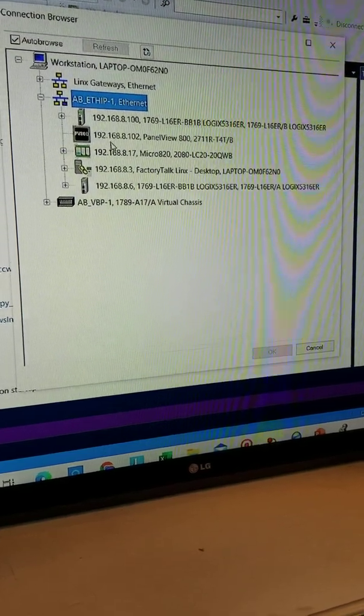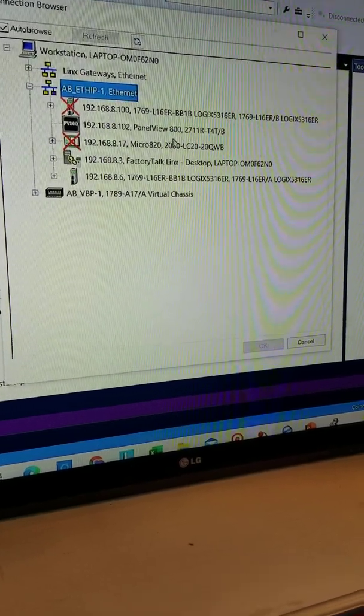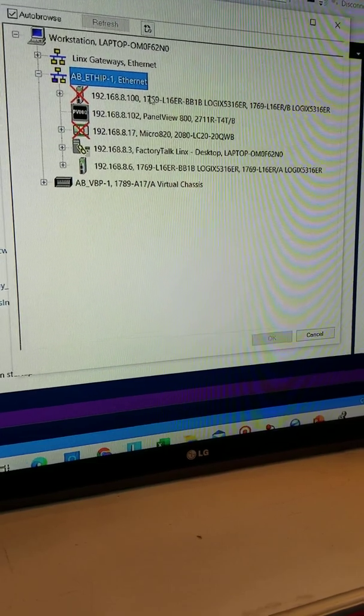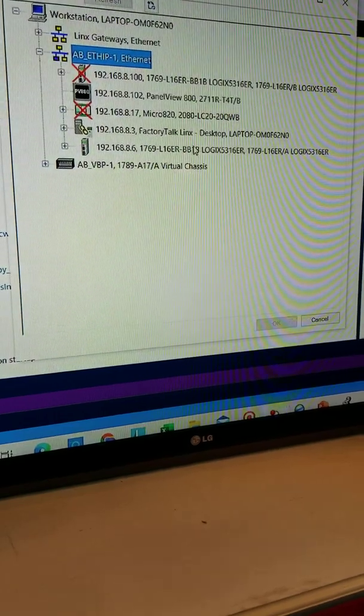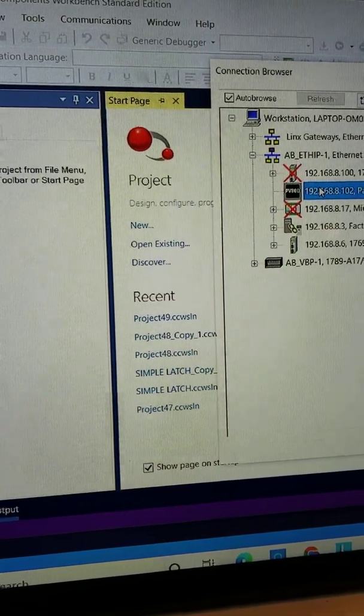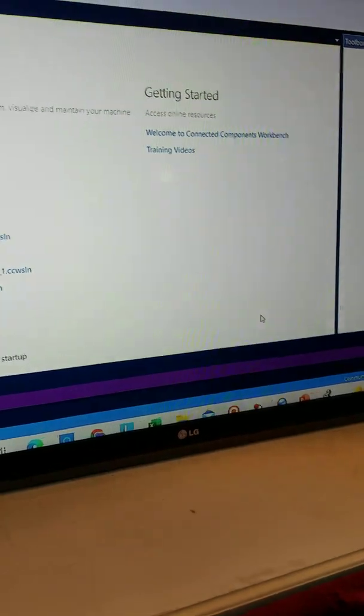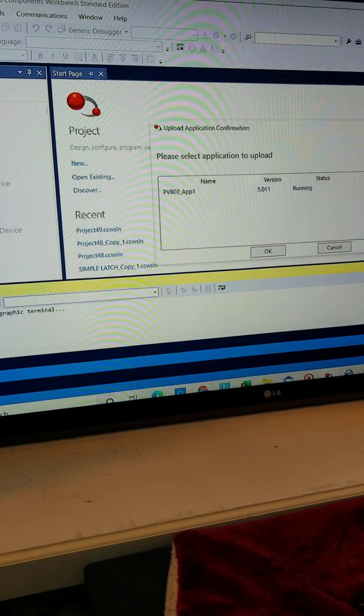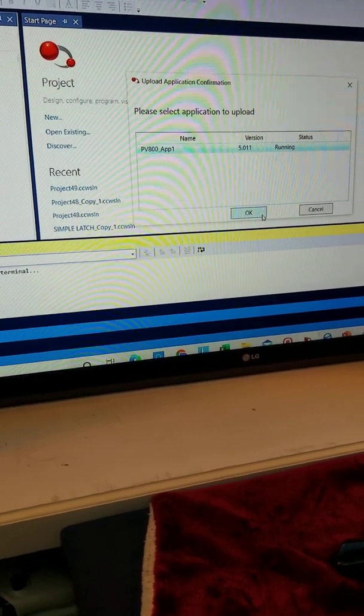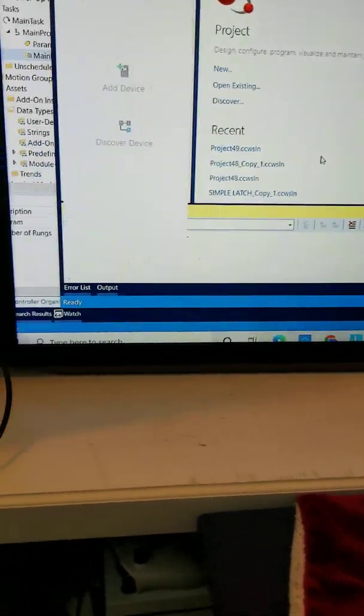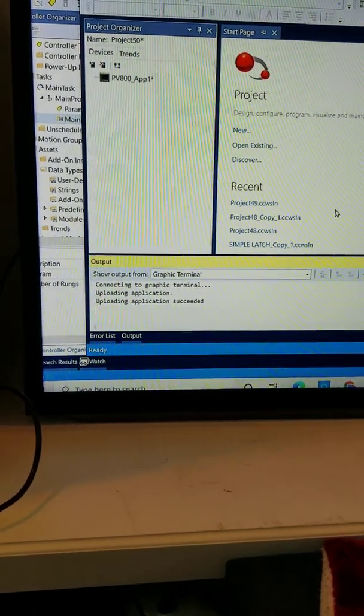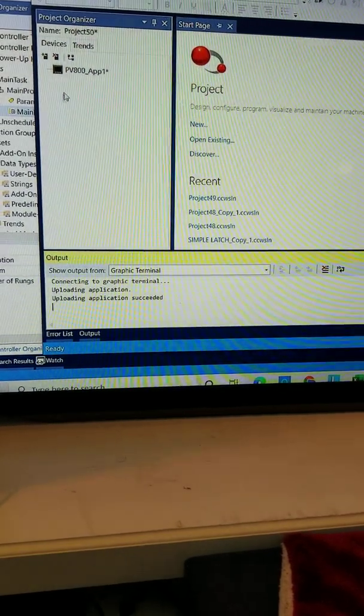Let's see what it sees. And it sees the Panel View, obviously that's it. It's looking for an old Micro 820 that was used and an old processor that had a different IP, but it found the IP address of the current CompactLogix we're using and it found the Panel View. So we're using Connected Components Workbench, that's the software used for the PanelView 800. So let's see if it opens it up for you. And right now the software is calling it, it's found it and we want to say okay. Let's see what it does. Upload overwrites, well we don't have nothing, let's do it. It says uploading, it's uploading. It says uploading application succeeded.